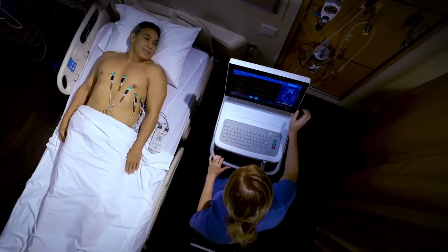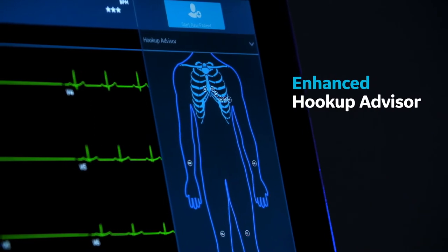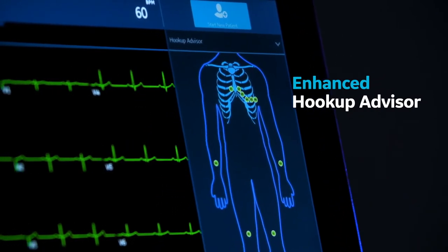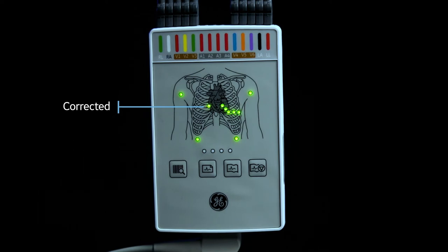Clean waveforms are vital in an ECG system. The MAC-VU360 Enhanced Hookup Advisor takes the guesswork out of getting a clean and high-quality waveform. It identifies signal quality and immediately notifies the healthcare provider of a poor connection.